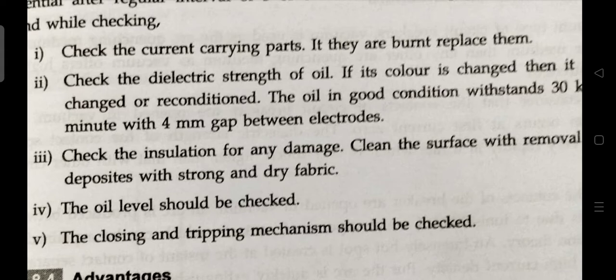Second, check the dielectric strength of oil. If its color is changed, then it should be changed or reconditioned. The oil in good condition withstands 30 kV for 1 minute with 4 mm gap between electrodes.